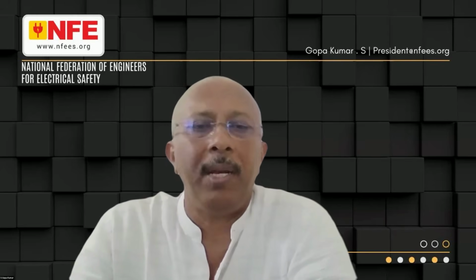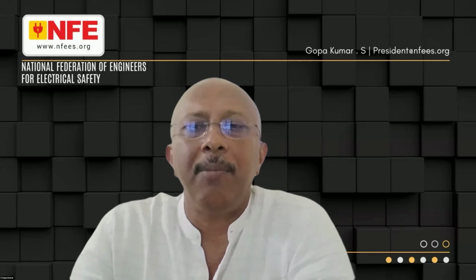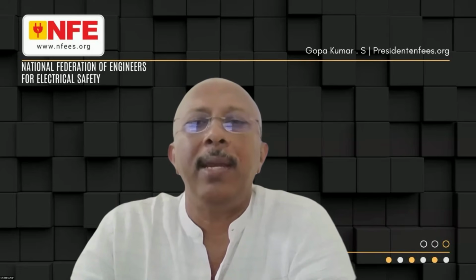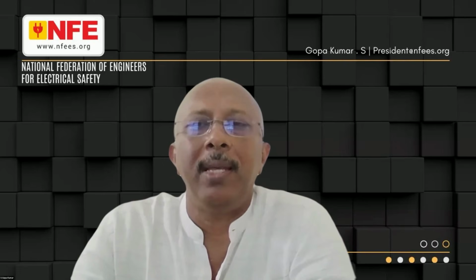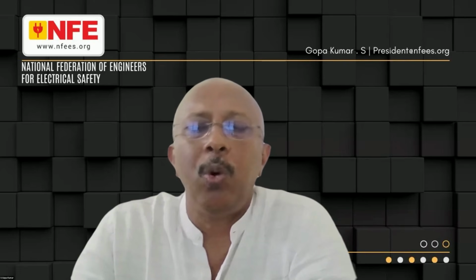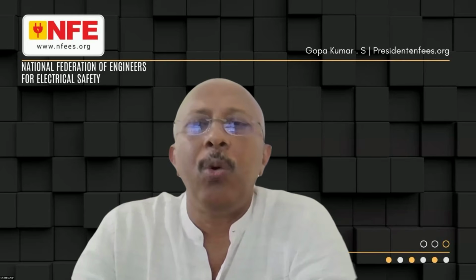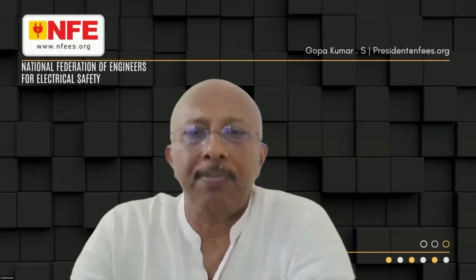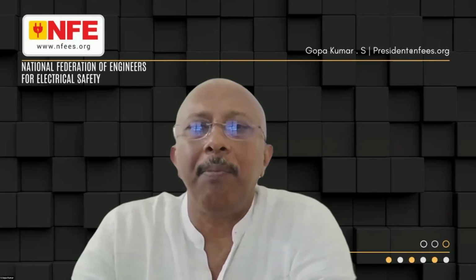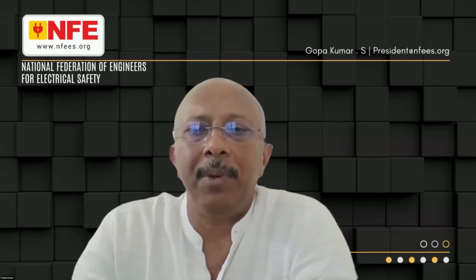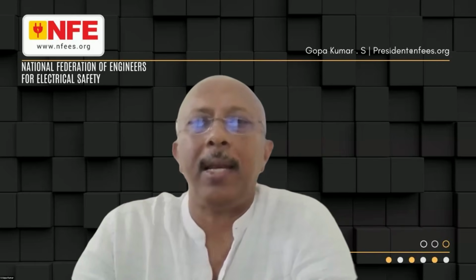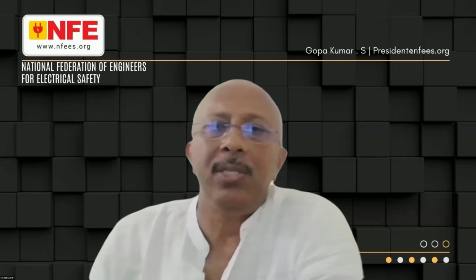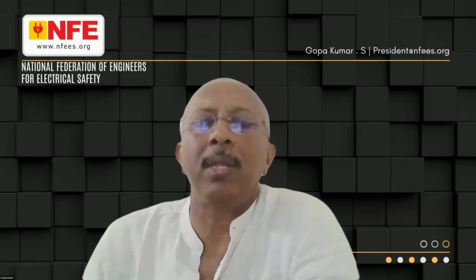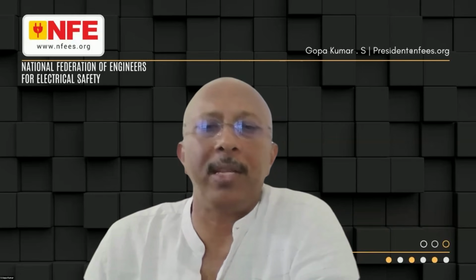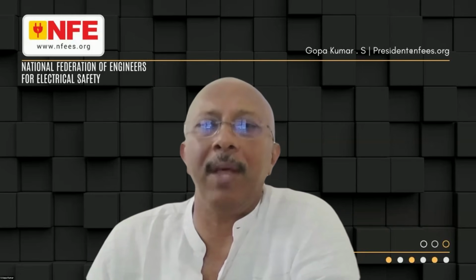And most of these equipment nowadays are having electronics and communication system. That means they are connected to a network. So it is communicating. The communication voltage is sometimes 2 volt, 3 volt, 5 volt, or 12 volt, very, very low voltages. And there is a subject of, let's say, clean earth, means an interconnected system, nothing to do with earth pit, an interconnected system which ensures that zero reference is maintained all over the building so that the functioning of the low voltage, extra low voltage equipment are smooth. There is no potential difference and they will work very well.